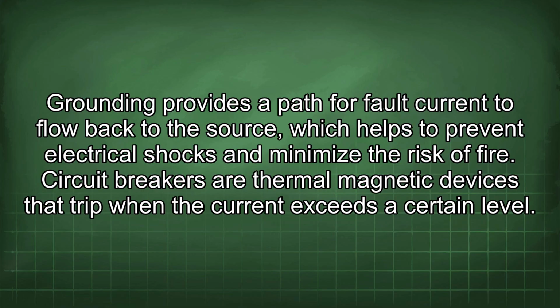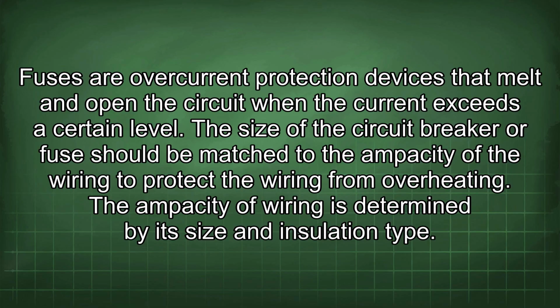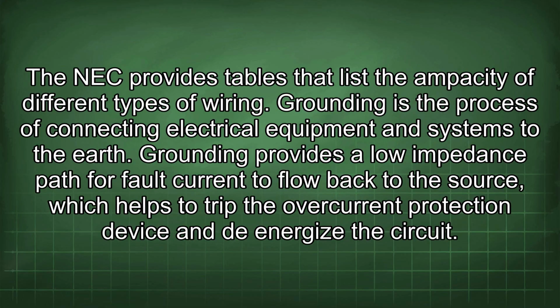Circuit breakers are thermal magnetic devices that trip when the current exceeds a certain level. Fuses are overcurrent protection devices that melt and open the circuit when the current exceeds a certain level. The size of the circuit breaker or fuse should be matched to the ampacity of the wiring to protect the wiring from overheating. The ampacity of wiring is determined by its size and insulation type. The NEC provides tables that list the ampacity of different types of wiring.